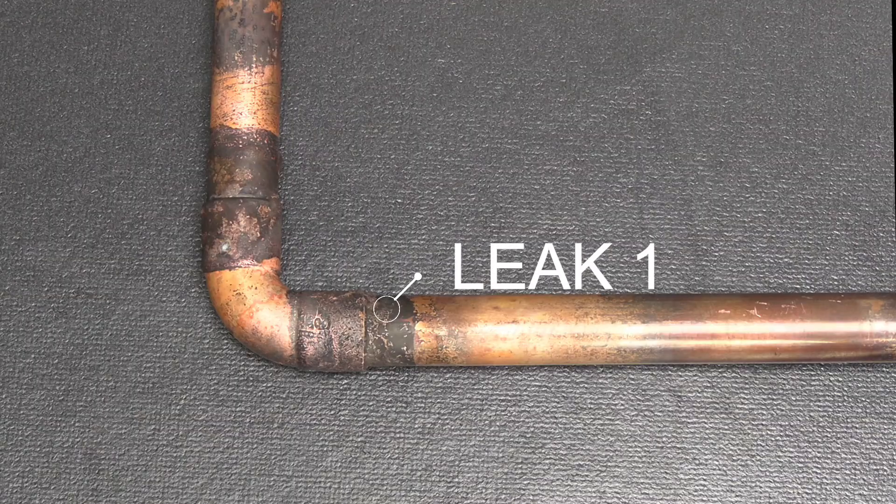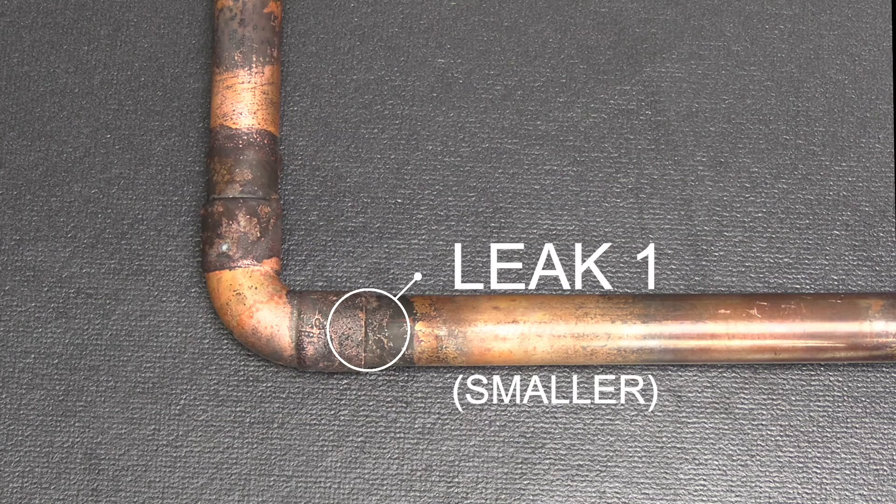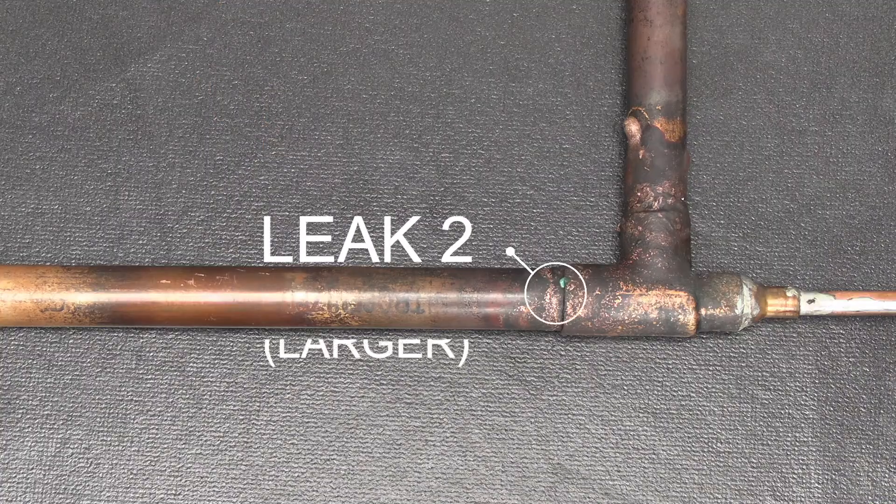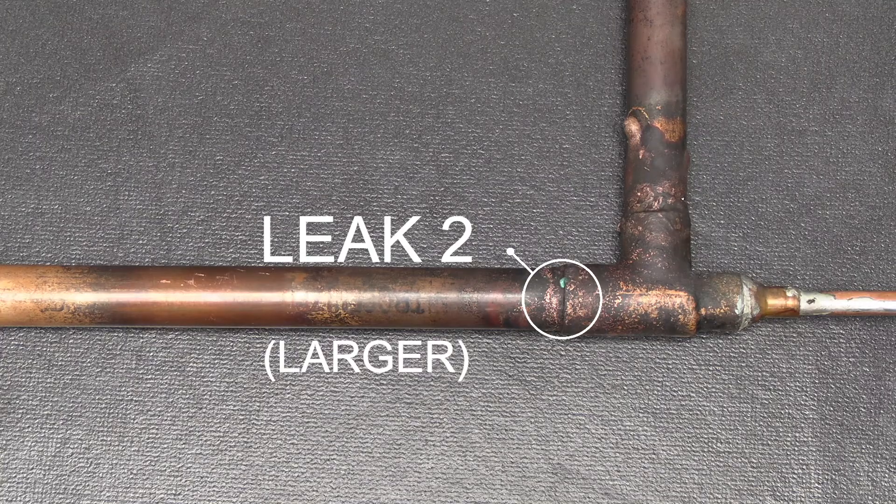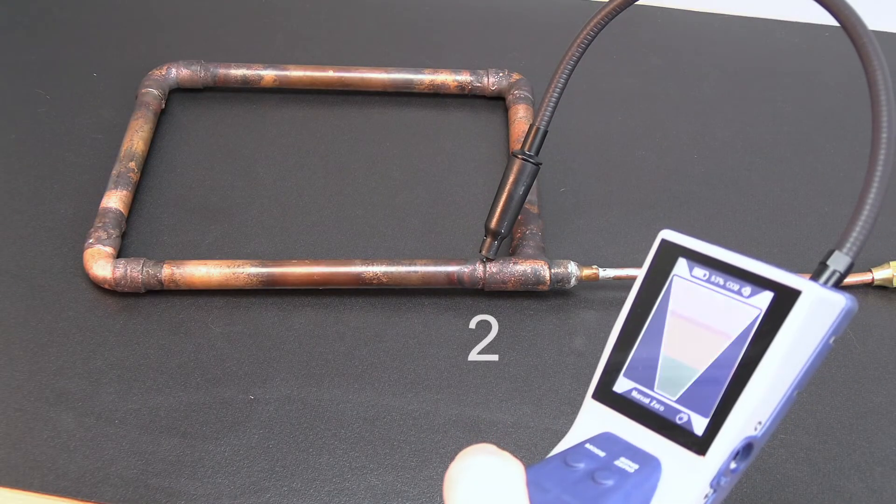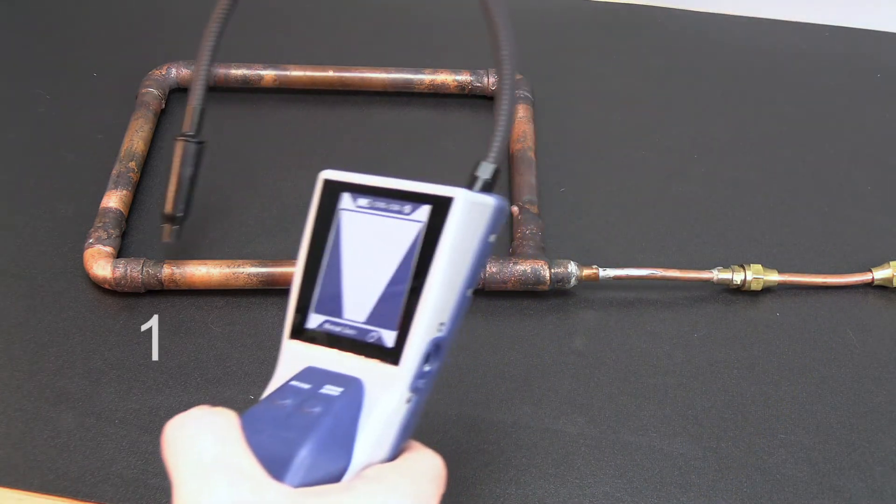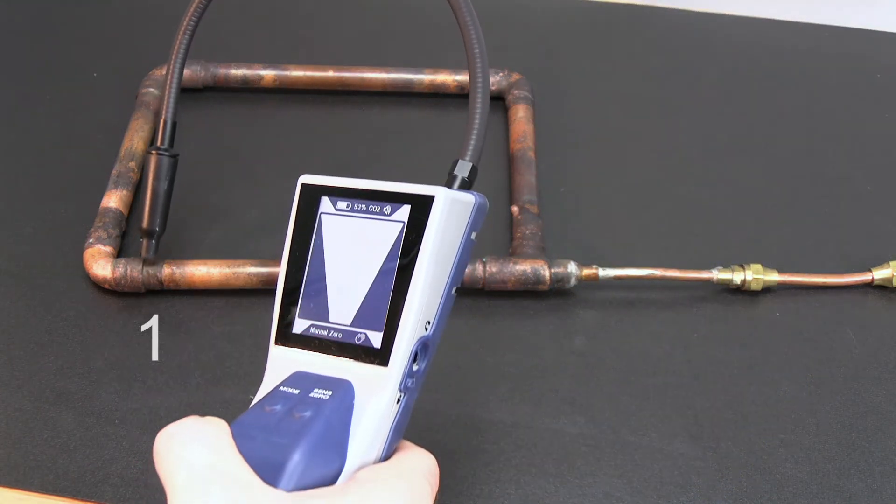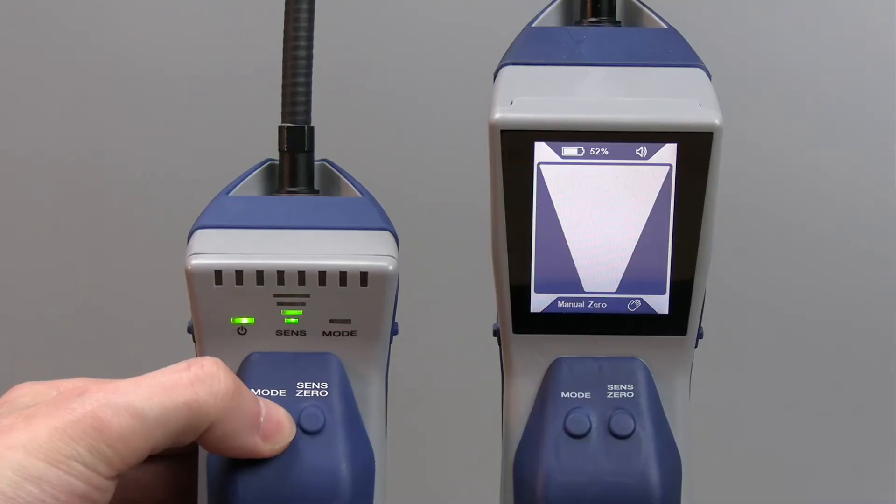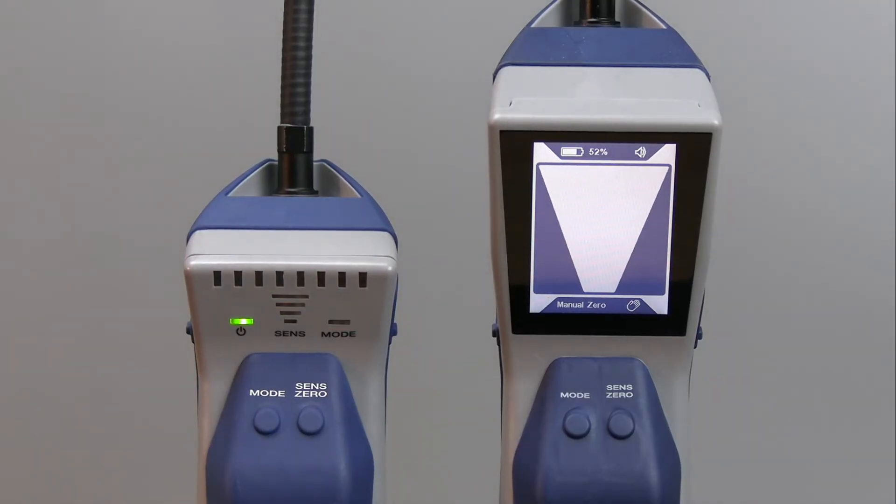Additionally, you can use Manual Zero Mode to compare more than one leak. Zero the unit on one leak and compare it to another to quickly determine which leak is largest. Note that you cannot adjust the sensitivity settings while in this mode.